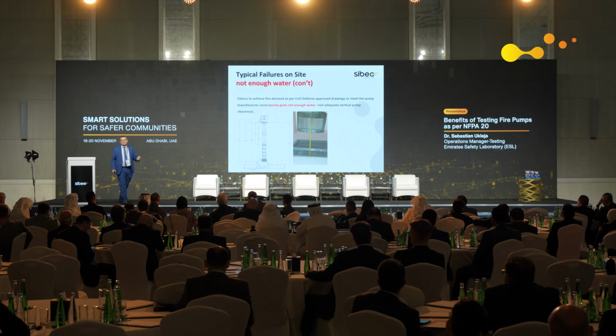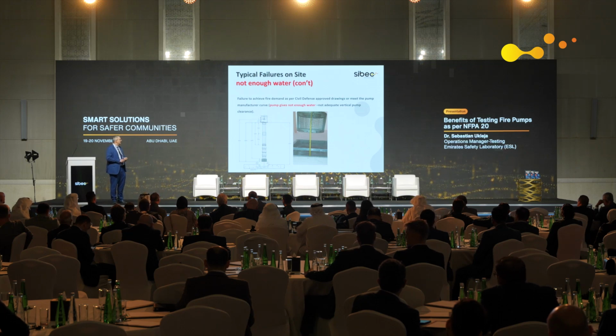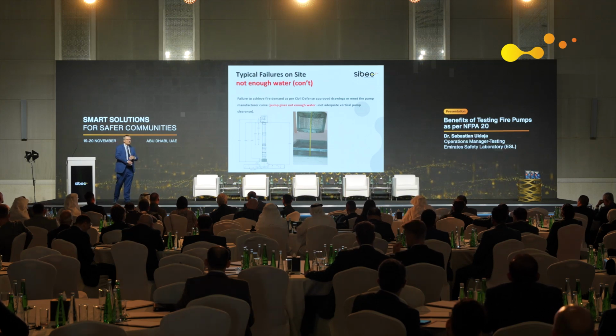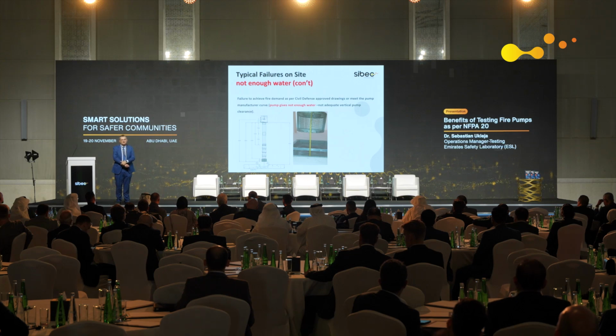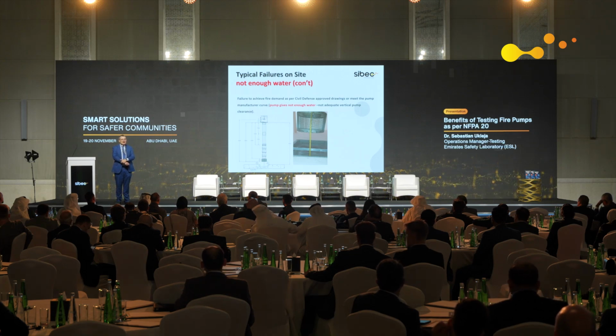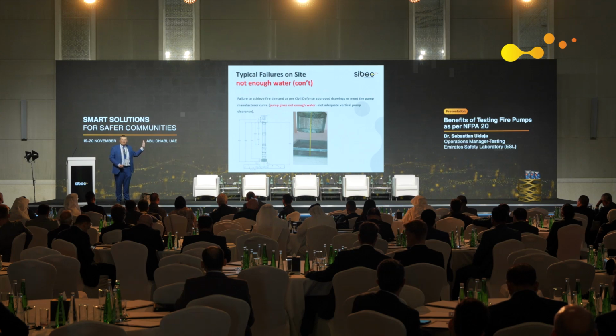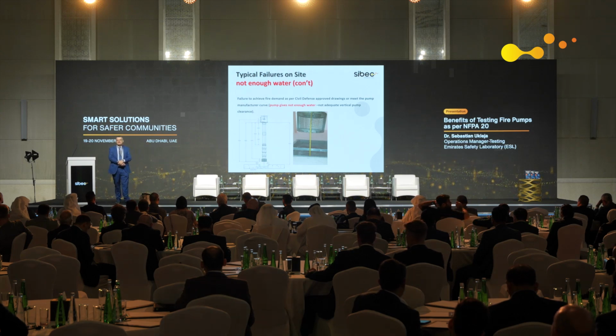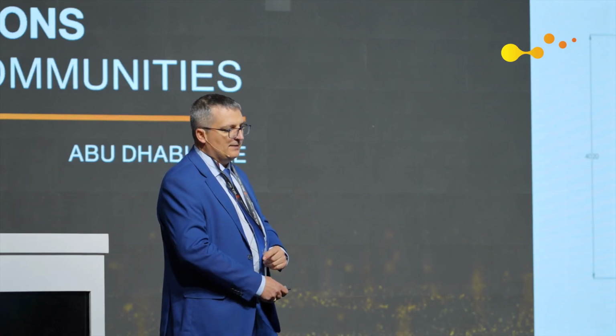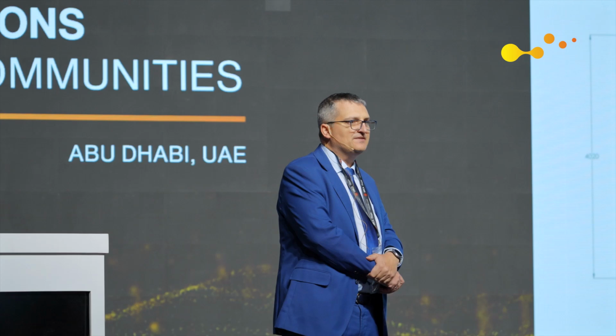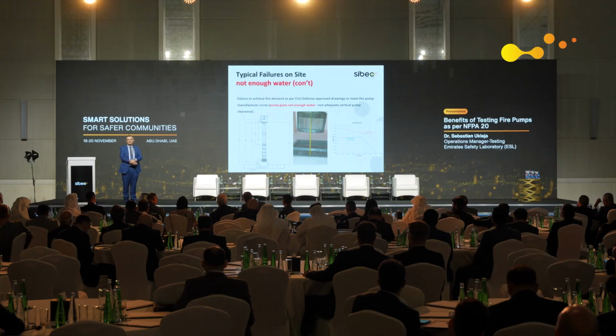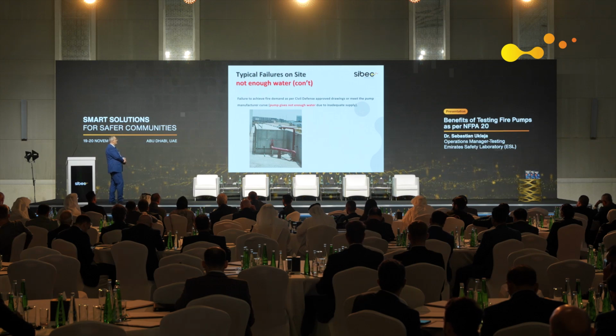Another example, as I said, pump is not getting enough water, because this is an example of a vertical turbine, and really we saw it happening. The pump needs clearance below. And if it's improperly installed, it's nothing wrong with the pump. It's just how it's installed in the water tank. If there is not enough clearance, the pump will not deliver the amount of water required. And then it gives the situation that the delivery water is below the requirements for a given pump.